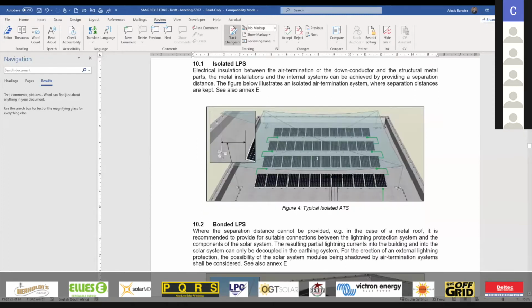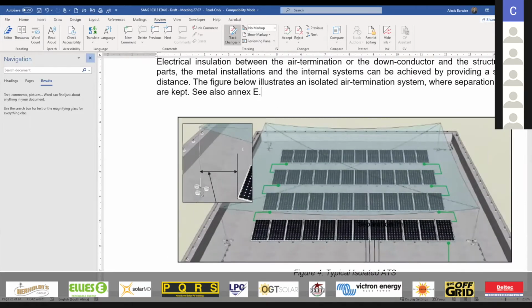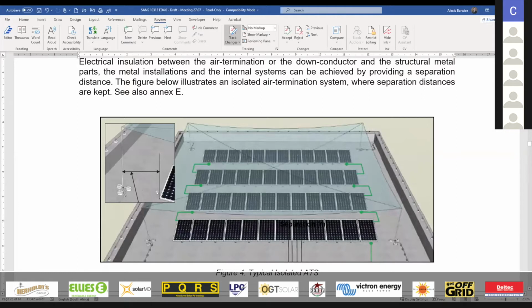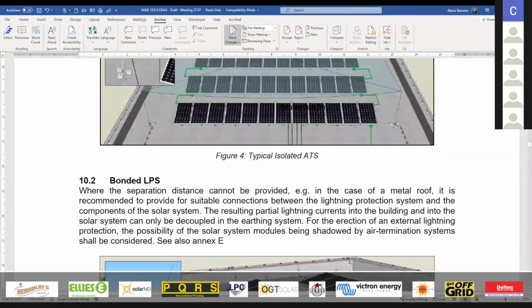Here you can see an example of it. I'll zoom in a little bit more. Maybe I can just close that. So you can see that there is a mast placed adjacent to the panels, and you can see these masts are all adjacent to the panels. Definitely an option on concrete type buildings with parapets, where we've done one example. Wits University looks very, very similar to this. And in this sense, what's going to happen is lightning will strike the mast. It will then go to the reinforced concrete, and we will test the continuity down to earth, and that will then take the lightning currents down to the earthing system. Then we only have to deal with the induced effect that strike would have on the PV system, and that's when we will start doing the bonding, as you can see here, but the bonding will be done by a 6 mm², because it's not carrying any lightning currents.